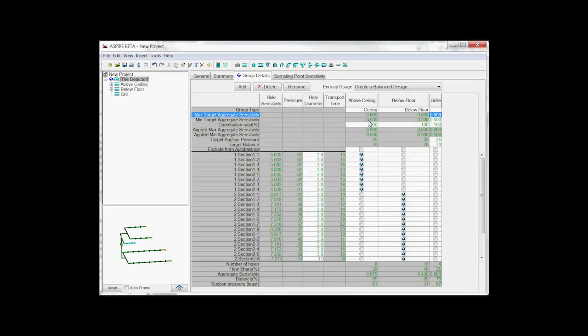In fact, there's one field here which is contribution ratio, and I just wanted to explain that one. Contribution ratio kicks in where you have a large room. In a large room, if there was a fire incident, the fire would be unlikely to contribute to 100% of the holes, because the smoke is going to be picked up by a certain proportion of the holes.